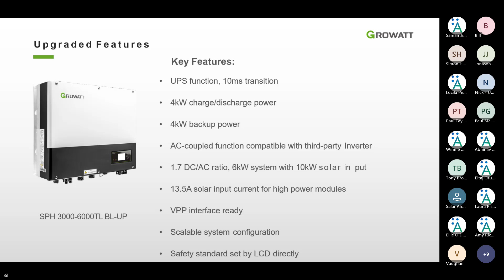Now here's the ALP, the new battery. As I mentioned, it comes with a heating pad and will support battery operation from -10 to 50 degrees, IP66, at 5 kilowatt hour each module up to 40 kilowatt hour. Since it's 0.75C, that means one battery will be able to charge and discharge around 3.75 kilowatt.